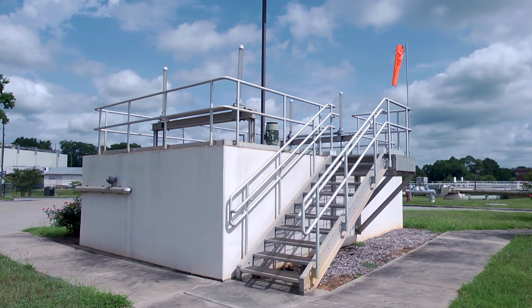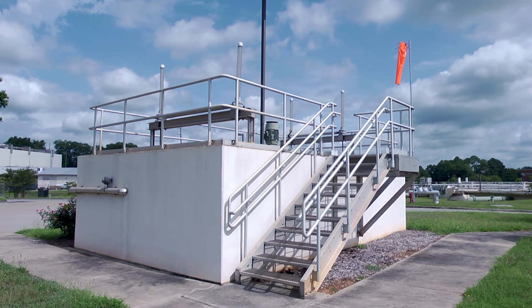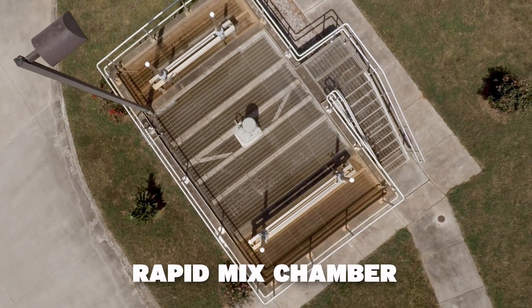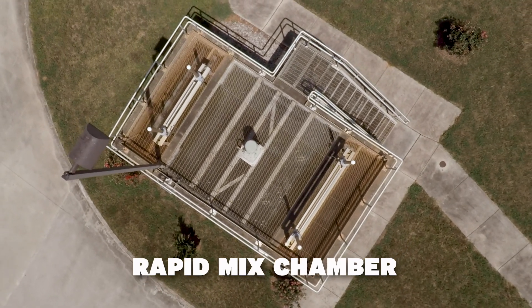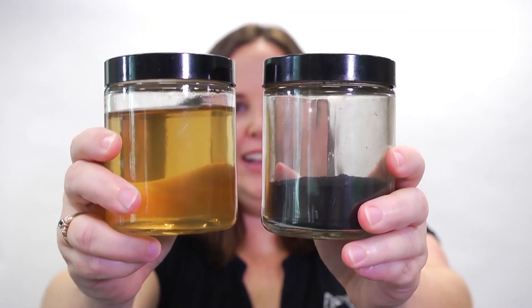The first stop for the raw water entering the water treatment plant is the Rapid Mix Chamber. This is a 15-foot deep basin with a huge mixer in the middle. The raw water is rapidly stirred to get all the silt, sand, clay, and dirt particles suspended in the water mixed up nicely with our first round of treatment chemicals — that's our powdered activated carbon and alum.